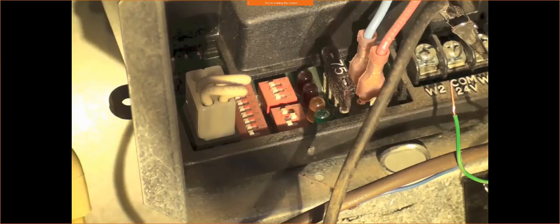You as a technician are going to be able to open up the furnace, and you're going to see this hard lockout code. The first thing you want to do, when you get to a system with an issue, besides checking the air filter, is see what that code is. As soon as you turn power off to the unit and turn power back on with these older types of systems, you're going to erase that code and you won't be able to recall it. And so you're starting from scratch. That system may reset when you turn the power off, and it's going to operate like it never had an issue. We don't know what the issue was, and so it may be hard to diagnose. But before we do anything, we're going to see what that hard lockout code is, and that'll help us determine what's going on. He also talked about the pressure switch.